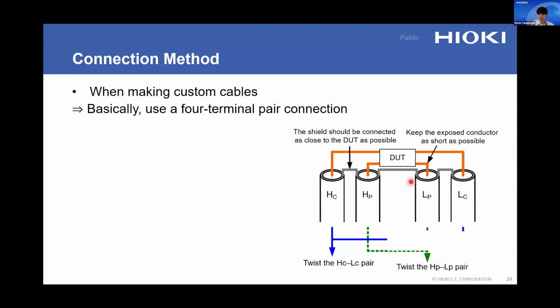This connection point should be placed as close to the DUT as possible. This makes the connection more effective. Also, as mentioned earlier, twisting the cables is effective. In addition, there are specifications for cable capacitance, so please refer to the instruction manual for each product for details.